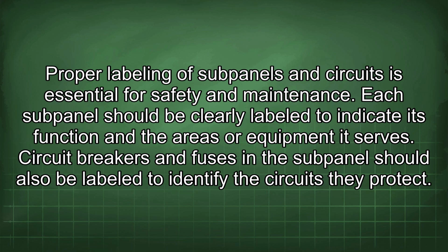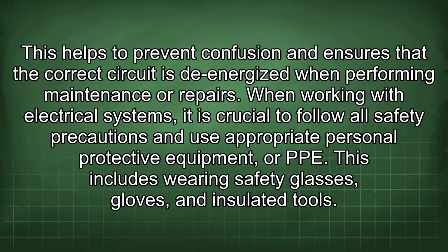Proper labeling of subpanels and circuits is essential for safety and maintenance. Each subpanel should be clearly labeled to indicate its function and the areas or equipment it serves. Circuit breakers and fuses in the subpanel should also be labeled to identify the circuits they protect. This helps to prevent confusion and ensures that the correct circuit is de-energized when performing maintenance or repairs.